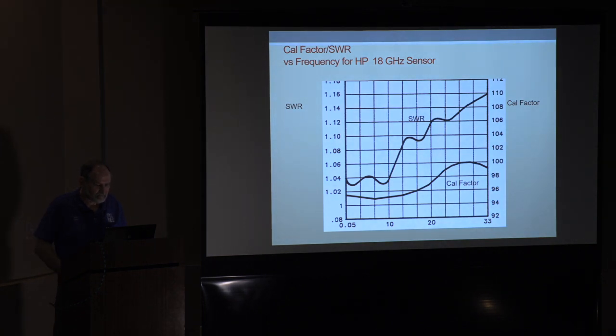This is an HP 18 gigahertz sensor, and the SWR goes to 1.16 up to 33 gigahertz. That's not too bad. And the cal factor doesn't go bananas. Now, I know taking an N connector and running it up to 33 gigahertz is asking for trouble, but you might be able to get away with 24 gigahertz and have some kind of accuracy without, I'm not sure what modes you'd set up, but that's the sensor rating, and gives you some hope at 24 gigahertz rather than buying an extremely expensive 24 gigahertz sensor. The 18 gigahertz waveguide sensor works nicely at 24 gigahertz also. Okay, change the slide.